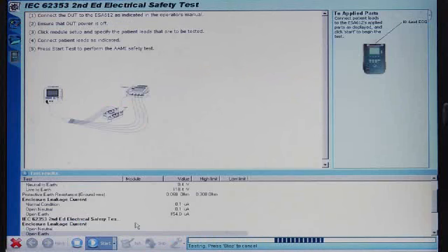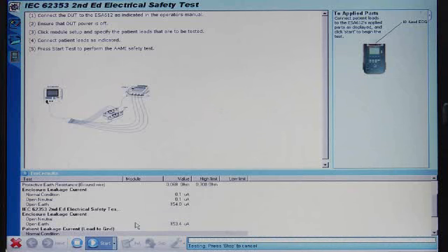Once we continue on, it performs the power on electrical safety tests, including any patient-applied part tests that need to be performed. In this case, because we're connected to a defibrillator, we will test the pads, the pacemaker leads, and all 10 ECG leads.